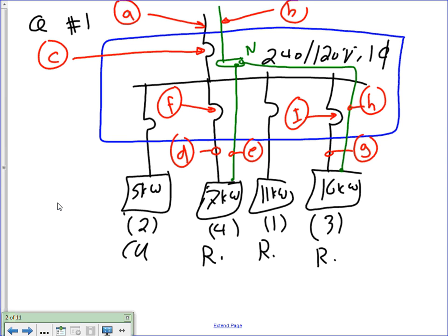There are a few questions, guys, about color code of ungrounded conductor, grounded conductor, and equipment grounding conductor. Everybody knows I can use pink as a phase, right? If you want to. The only limitation when you have ungrounded conductors, the phases, is you can't use green or gray or white, right? Other than that, you can use any color you want.